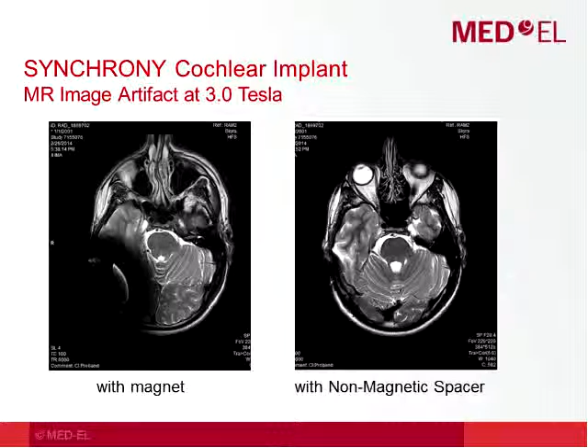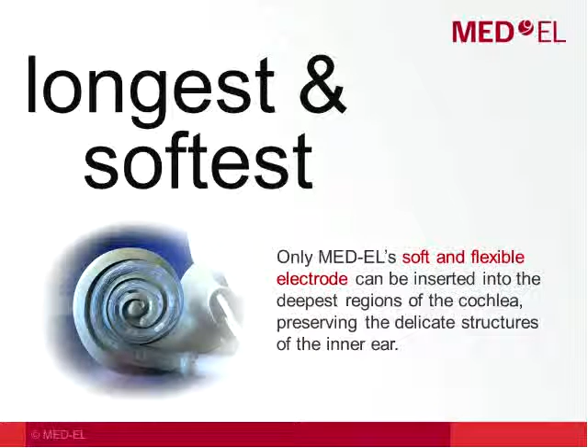I also mentioned that we try to have a very soft and flexible or atraumatic electrode array. It's very important to us that not only is the electrode soft and flexible enough that it can be inserted without damaging the inner ear, but it's also always been important to MED-EL that the electrode go as far into the inner ear or cochlea as possible. We want to stimulate as much of that inner ear as we can. So MED-EL has always had the longest electrode arrays, and we also work to have very soft and flexible electrodes so that they cause as little damage to the inner ear as possible.